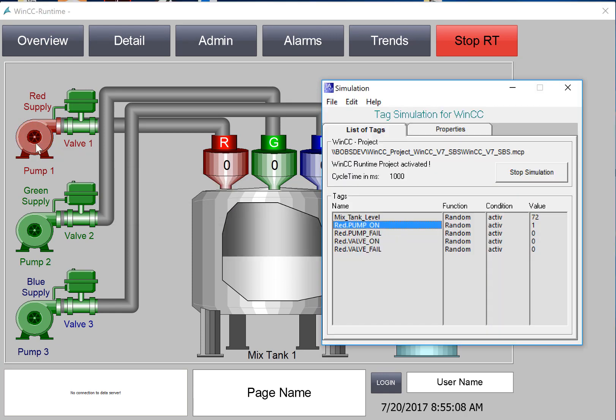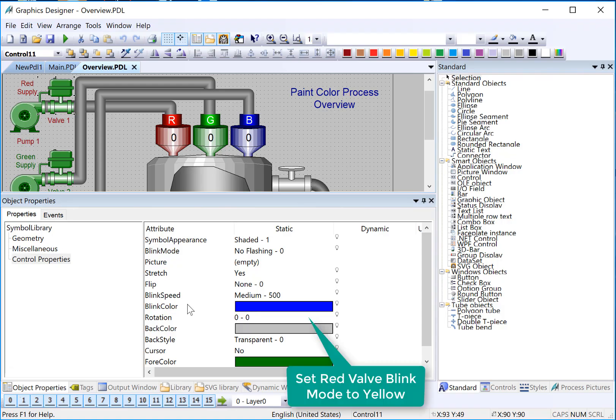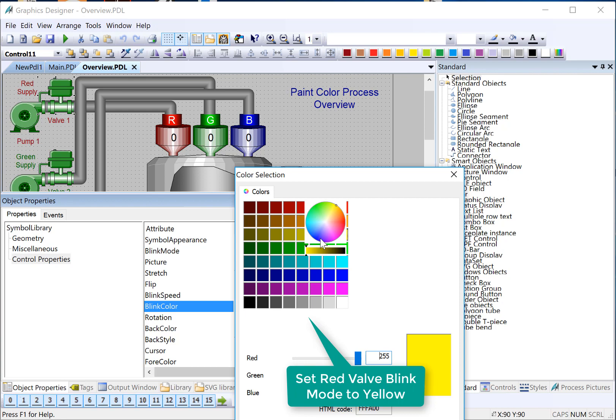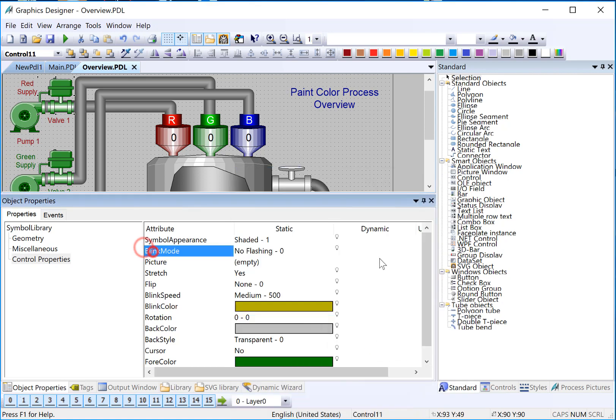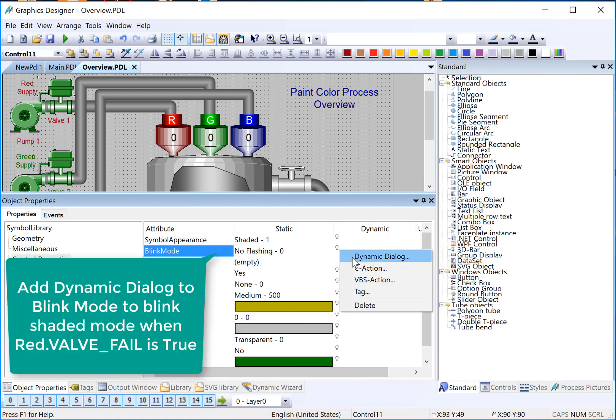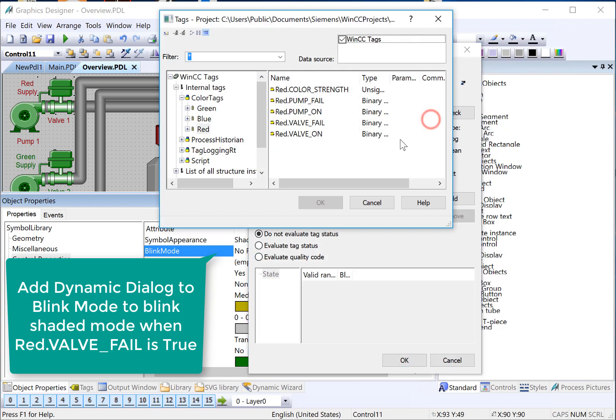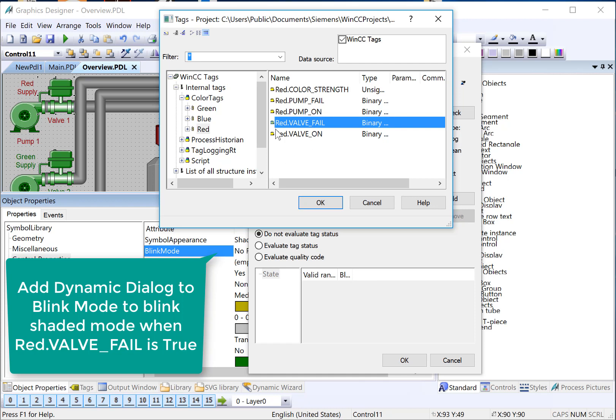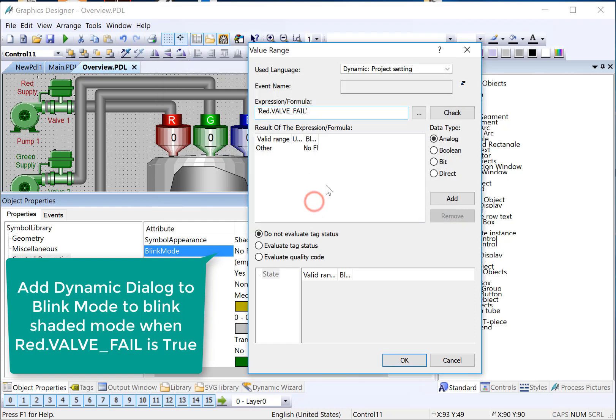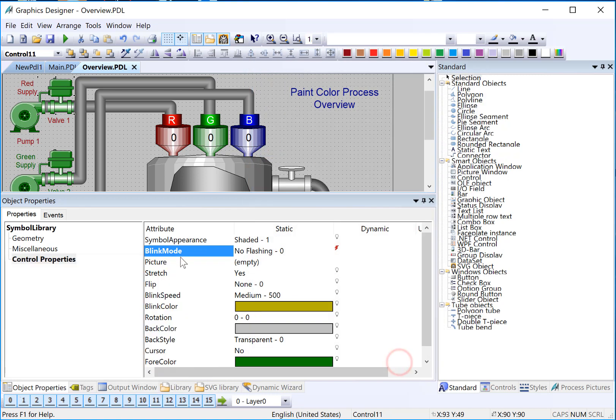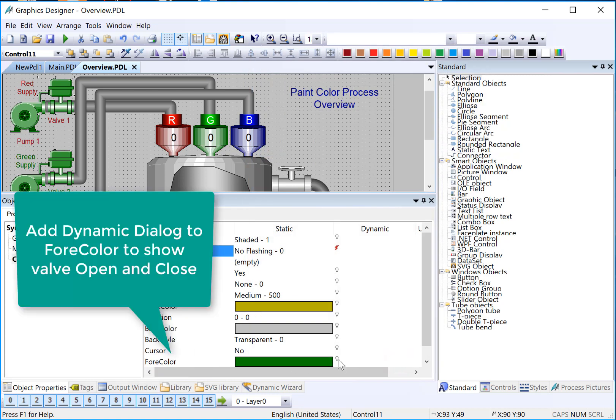So now we're going to do the same thing for our valve. So I'll choose the valve. We'll go ahead and set the blink color to yellow. On our blink mode, we'll choose our dynamic dialog. Our expression is going to be our valve fail since we're doing our failure mode. It's going to be Boolean. And then if it is in fail, it's going to flash between yellow and whatever the background color is.